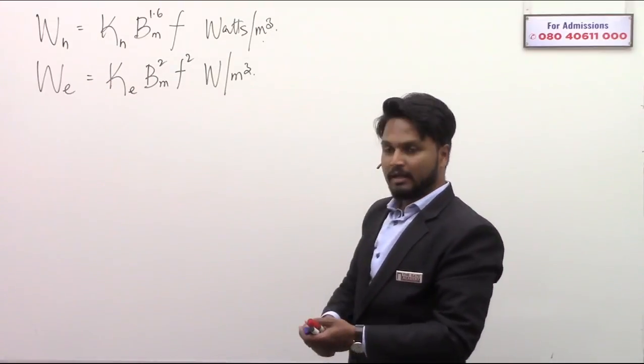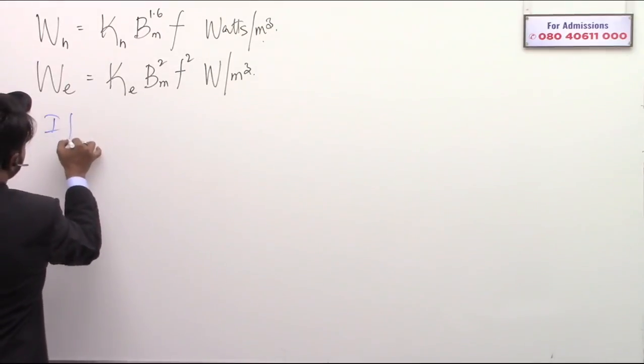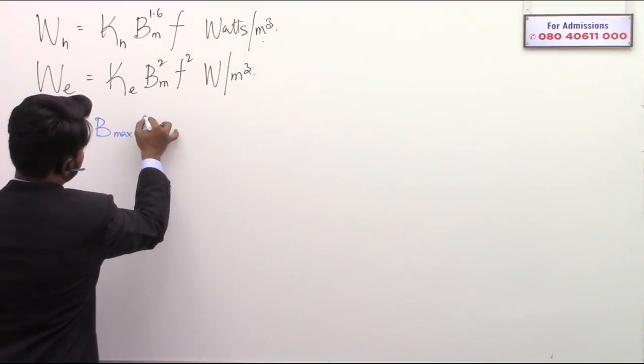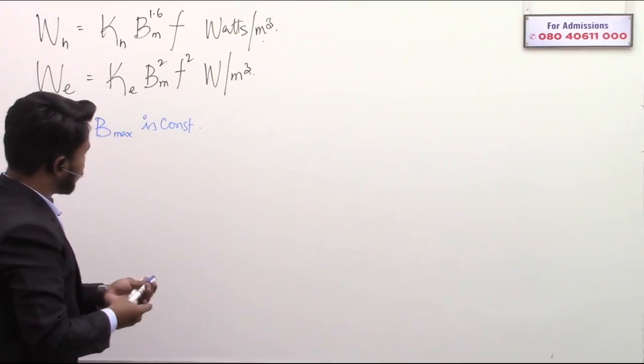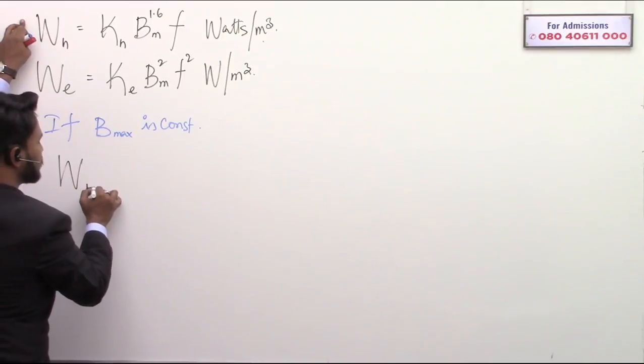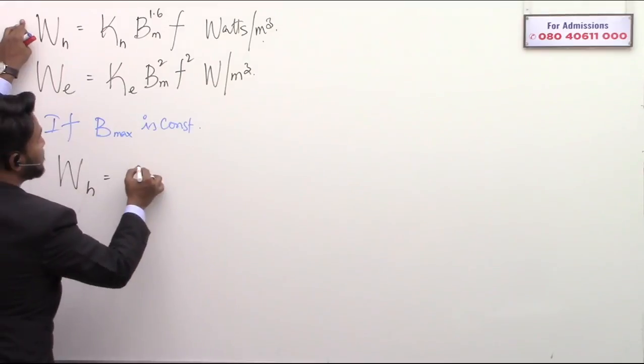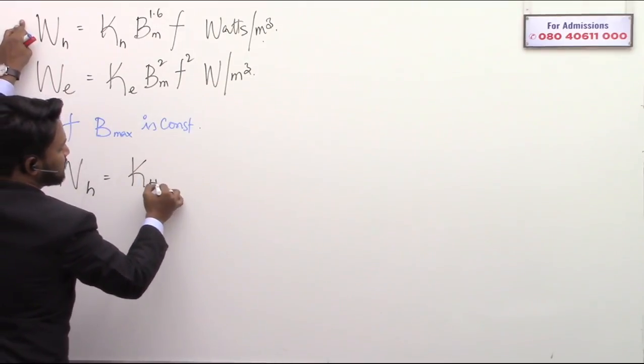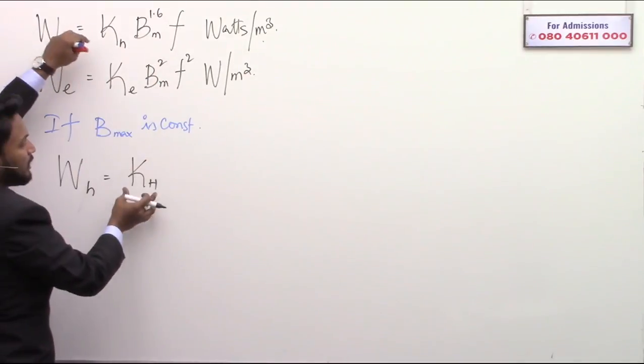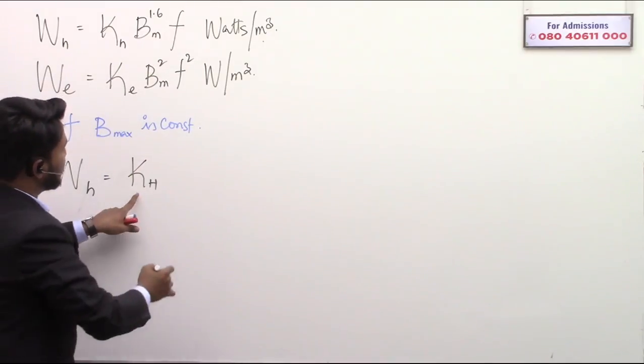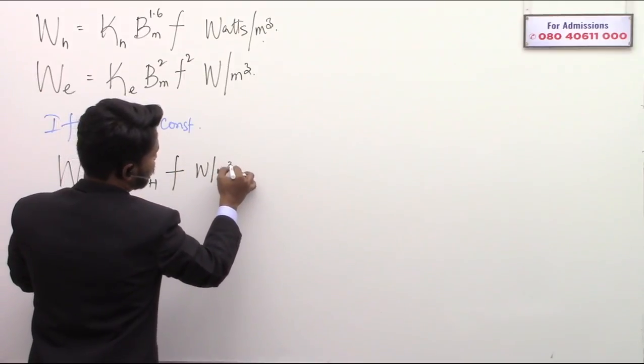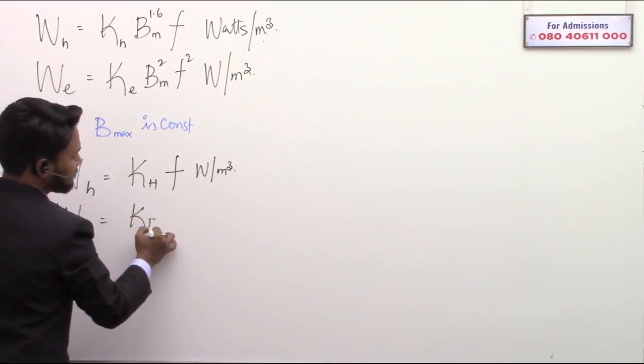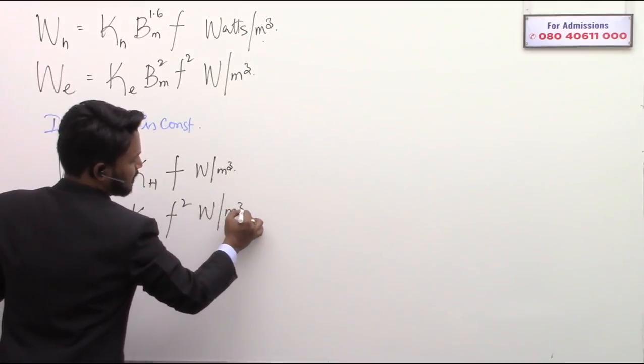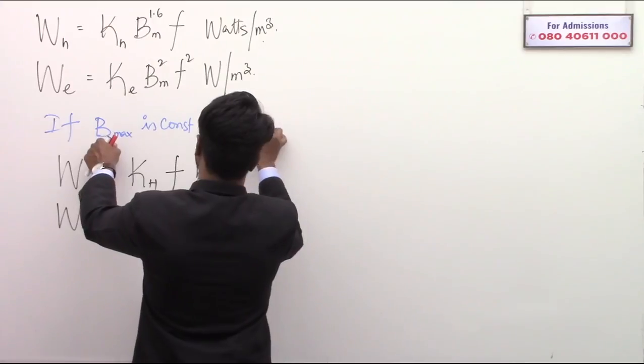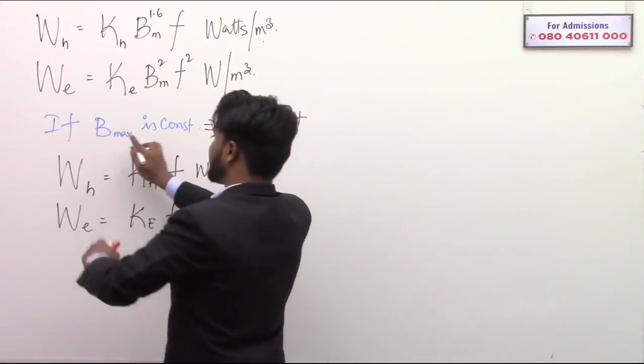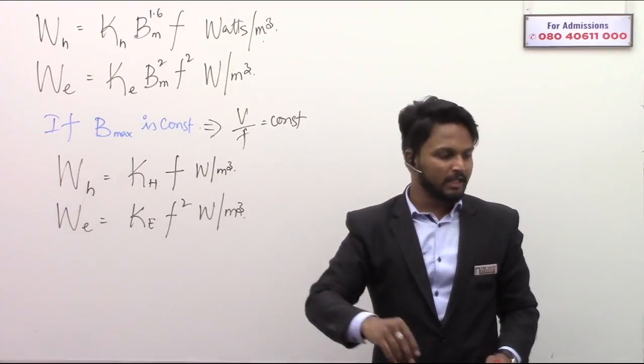Therefore, if B max is constant, hysteresis loss WH will be equal to some K suffix capital H. I'm including this B max multiplied by KH, and I'm considering it as KH. It is some KH into F watts per meter cube, and eddy current loss is equal to some K suffix capital E multiplied by F square watts per meter cube. Only if V by F is constant, then B max will be constant. So see whether V by F is maintained constant or not.